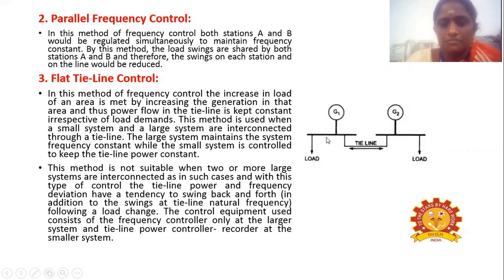The larger system maintains the system frequency constant, while the small system is controlled to keep the tie line power constant. The main drawback of this flat tie line method is that it is not suitable when two or more large systems are interconnected, because in this case the control of tie line power and frequency deviations may swing back and forth. The control equipment used consists of frequency control only at the larger system, and tie line power control and recorder at the smaller system.